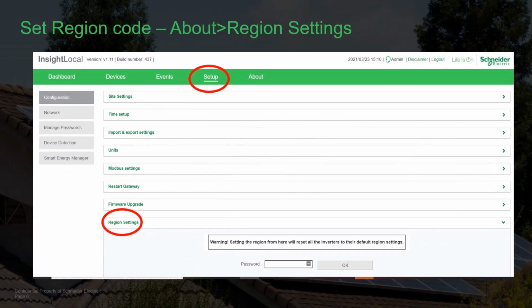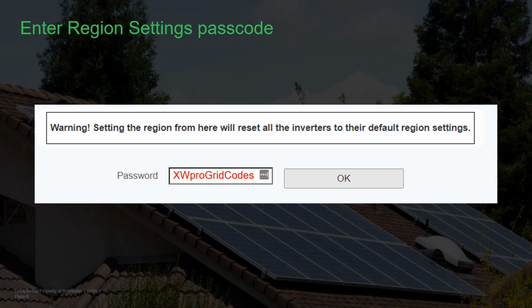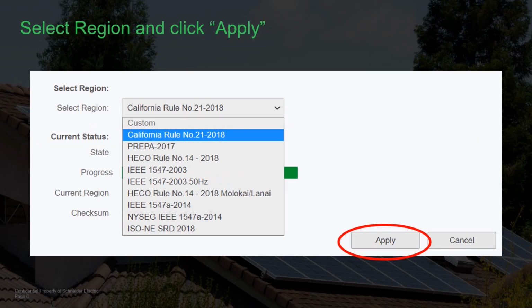After the latest firmware is verified on all units, click Setup, Region Settings, enter the Region Settings passcode, which is indicated on the screen, and click OK. Then select and apply the appropriate region code for your utility. Off-grid can select IEEE 1547. Each XW Pro has a dedicated grid code section that uses the same password. Verify the correct region code appears in XW Pro.